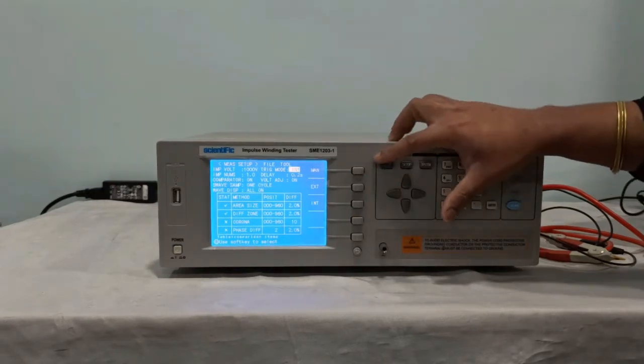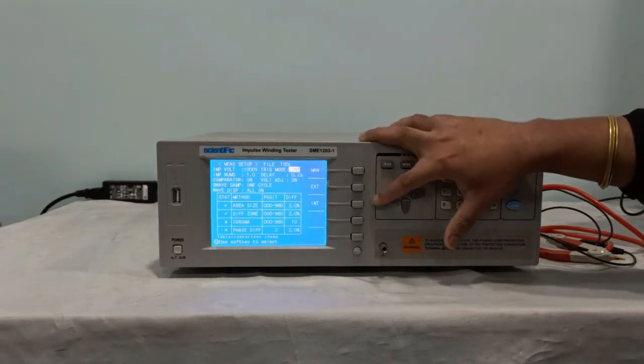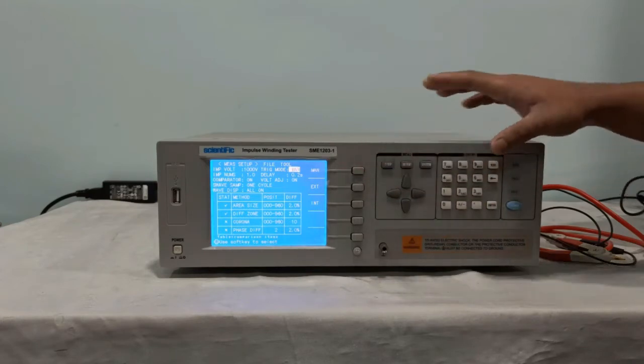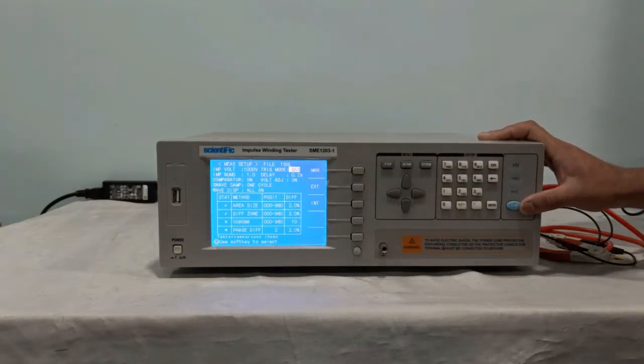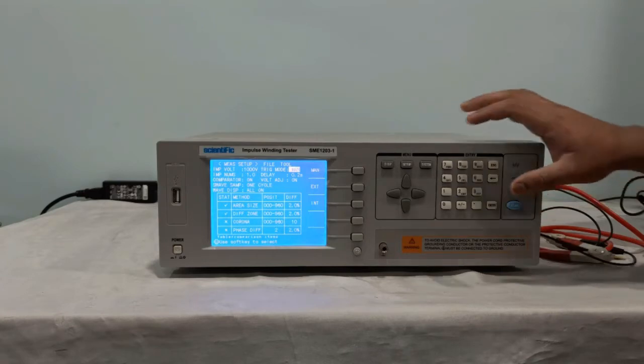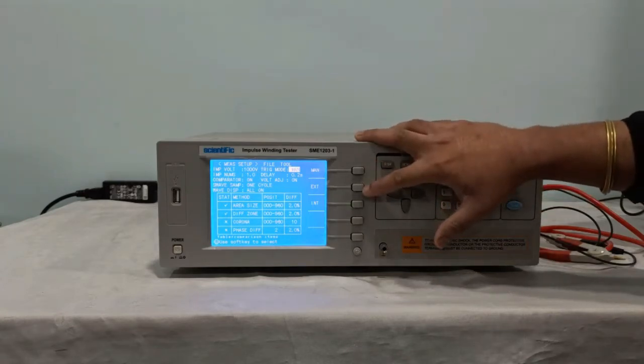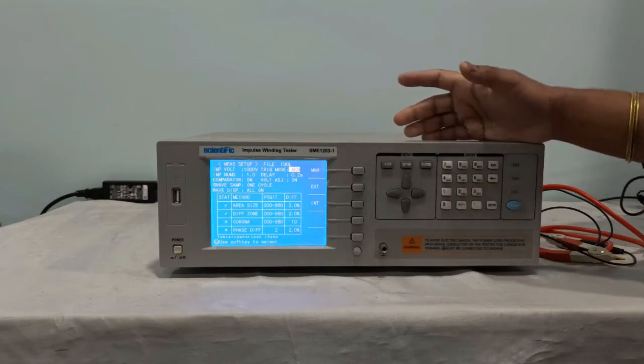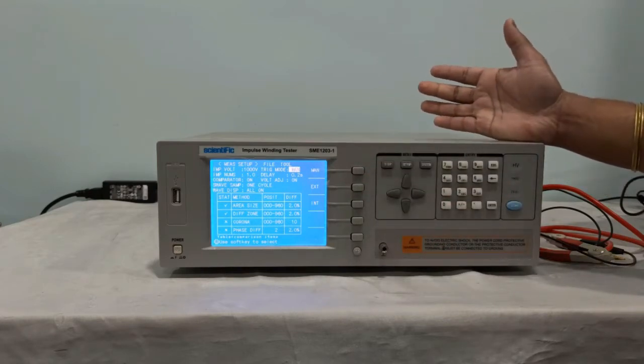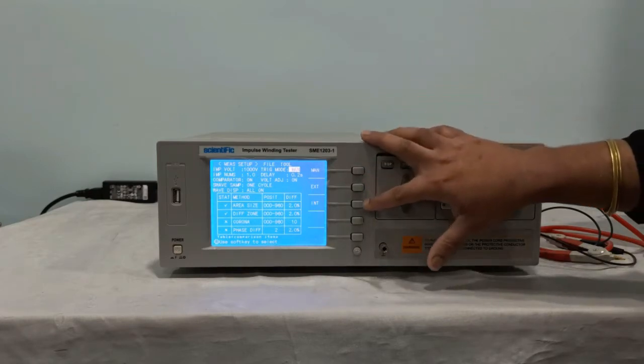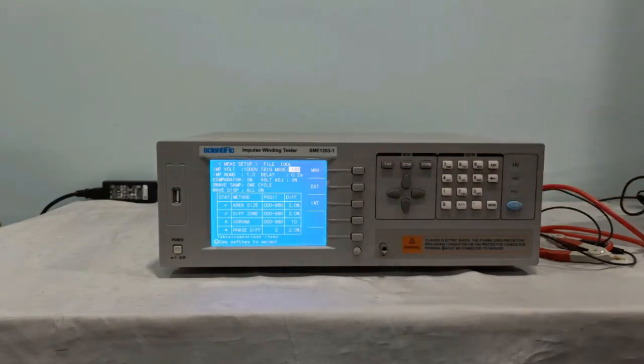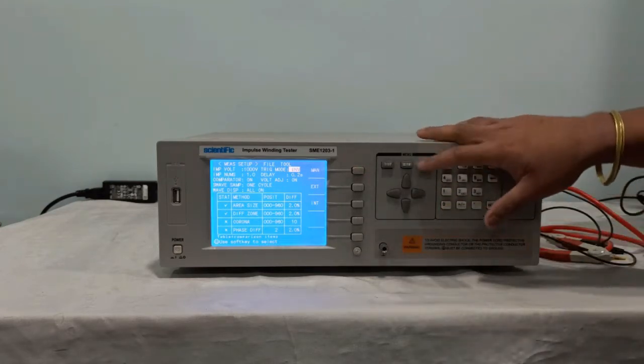Next we have trigger mode. We have 3 options here as manual, external and internal. If it is set to manual, whenever this start key is pressed, it will trigger the instrument. When it's set to external, you can trigger the instrument through handler interface or foot switch that is at the rear side of the instrument. If it is set to internal, here internal means the instrument will trigger once the start key is pressed and will continuously take the measurement until the start key is pressed again. So we are putting it to manual mode right now.